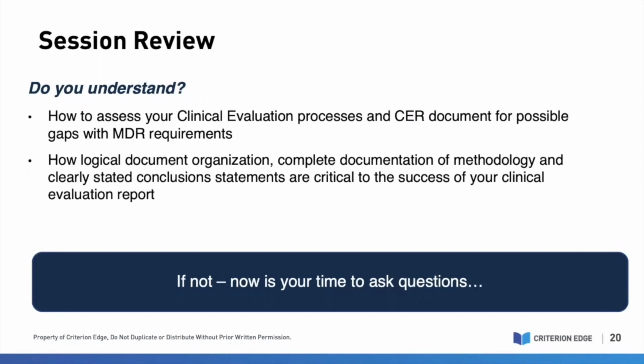You can't present specifically your own device data in the state-of-the-art section, but you can use systematic literature reviews and other sources of pooled and meta-analysis data in which your device may be included to establish the overall safety and performance criteria and acceptance, upper and lower bounds of acceptance criteria for the state-of-the-art. I hope that helped answer and clarify that question.